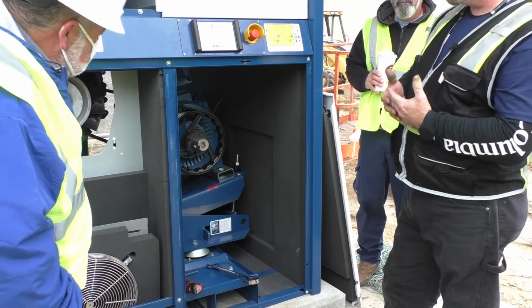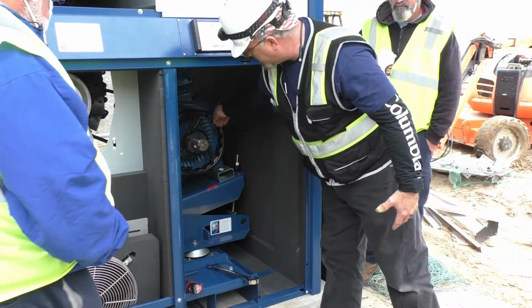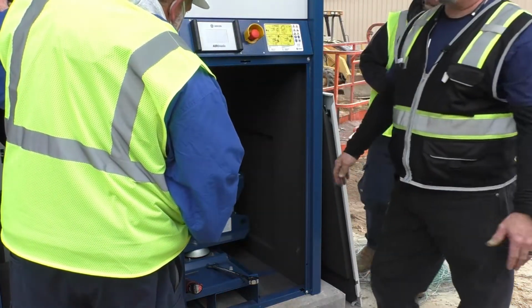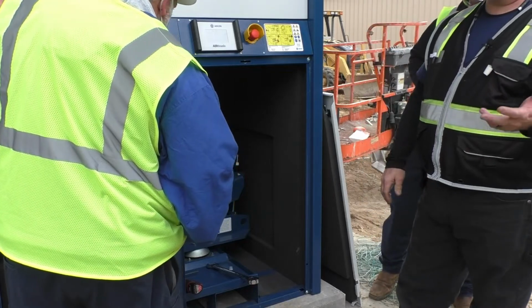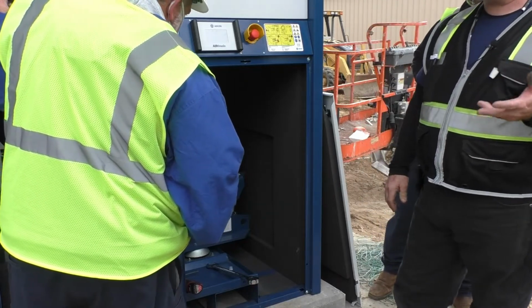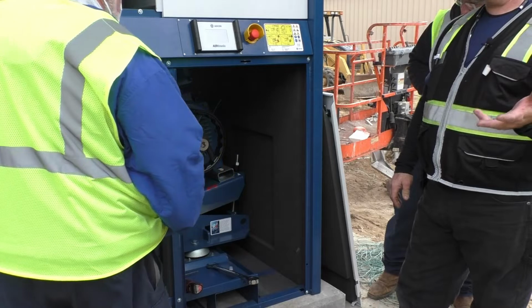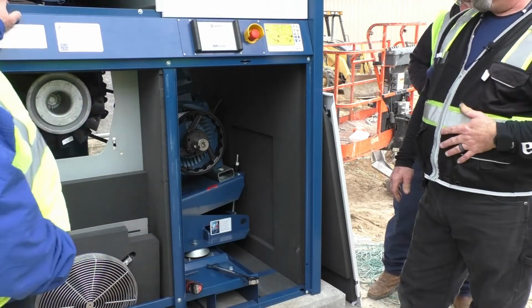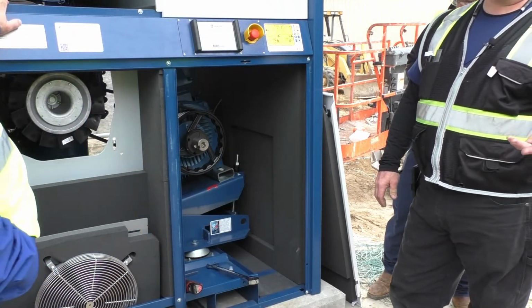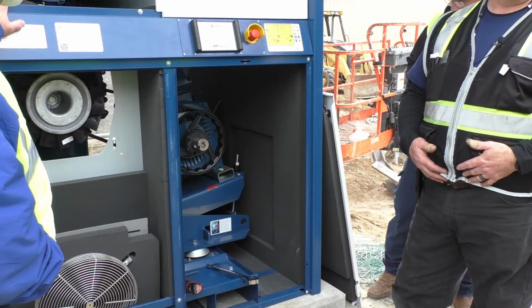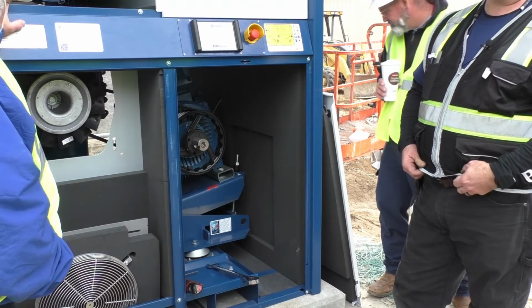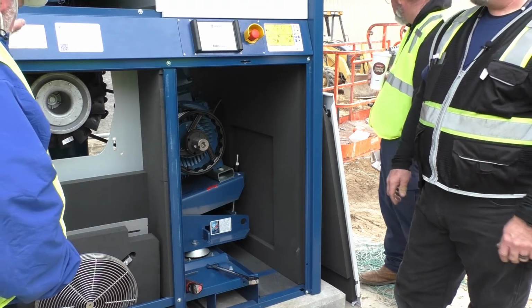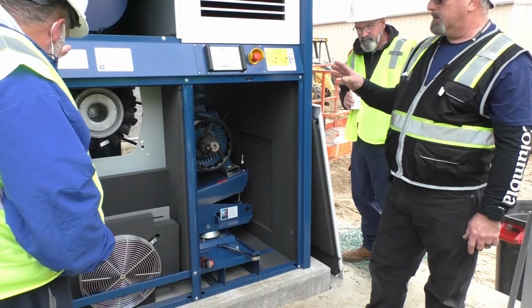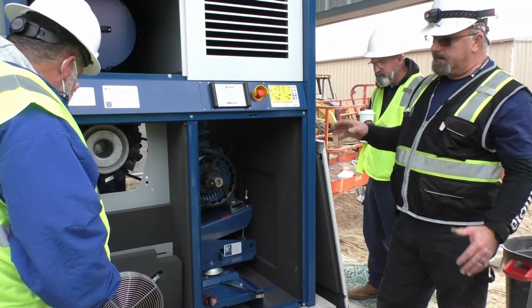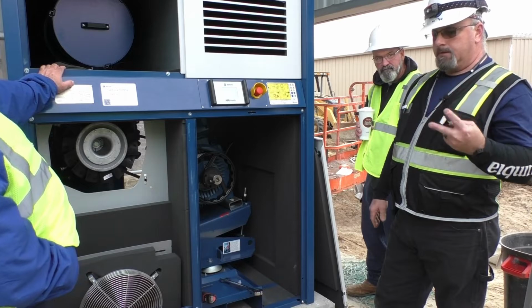You can use a straight edge across the face of your two pulleys. That will get you pretty close, usually within a 1/16 or less. That is acceptable. But if you have belt drive issues, you may have to resort to a little bit more accurate method. Now, and I stress that because if it does get out of alignment, two things can happen.